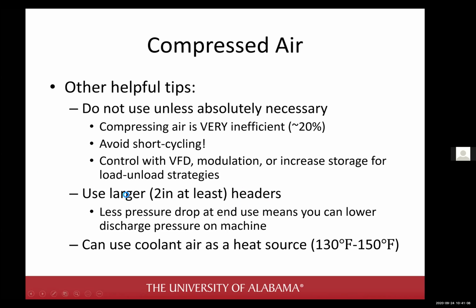Other best practices for compressed air: use as large headers as you can. The bigger the diameter of your headers, the less pressure is lost from compressor to the end use. So that means you can turn down your pressure and save 1.6% for every 2 psi.